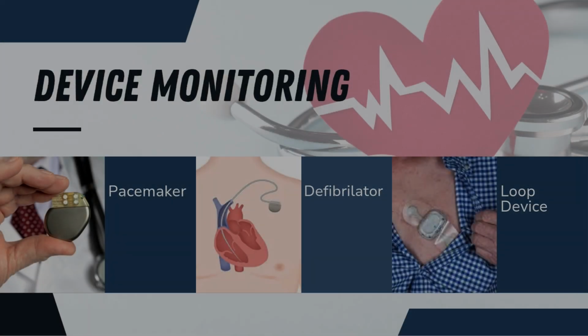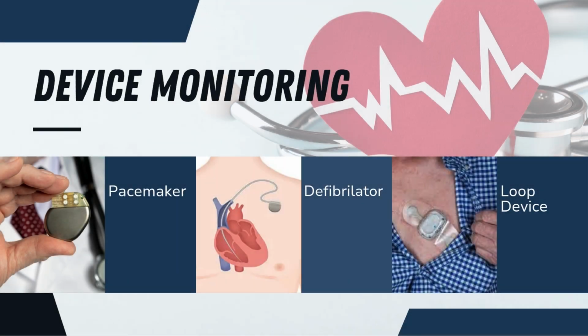What we're talking about doing is a deeper dive onto the functioning of the device itself. We can not only look at additional parameters beyond what the bedside box can do, but more importantly, we can make changes should we need to. I won't get into all the parameters that can be changed, but we can change those if need be. For most devices, pacemakers, defibrillators, if they're stable, if they've been in for a few years, once or twice a year would be adequate checks.